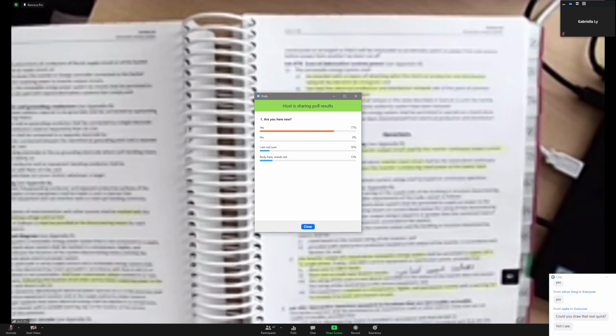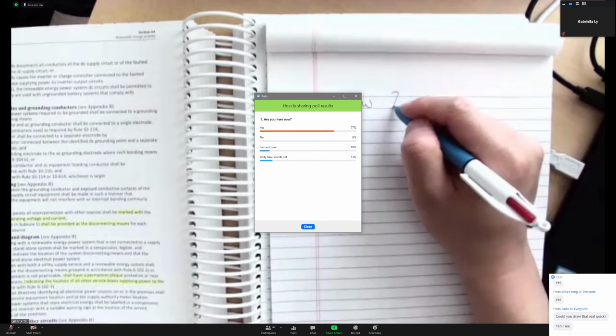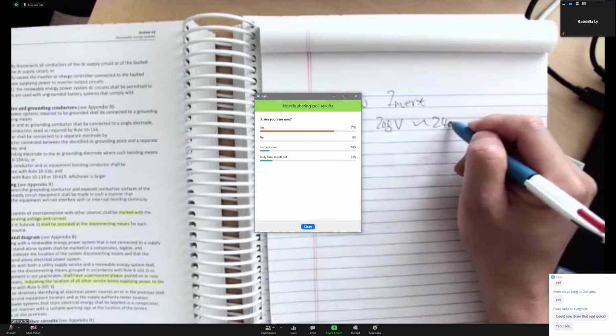Next one, the inverter. Maximum circuit loading: the maximum current of the inverter output circuit shall be the inverter continuous output current. The maximum current of a standalone inverter input circuit shall be the standalone continuous input current rating, where the inverter is producing rated power at the lowest input voltage. So I believe you guys have encountered a problem. Let's say you have a 6 kilowatt inverter. It's rated for, let's say, 208 volts to 240 volts. What's the maximum current?